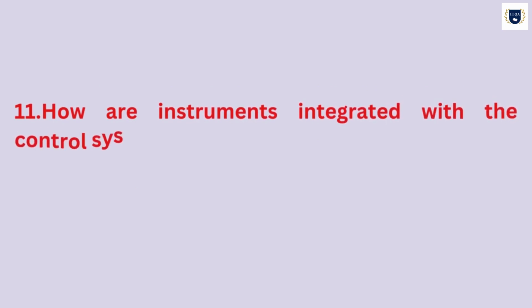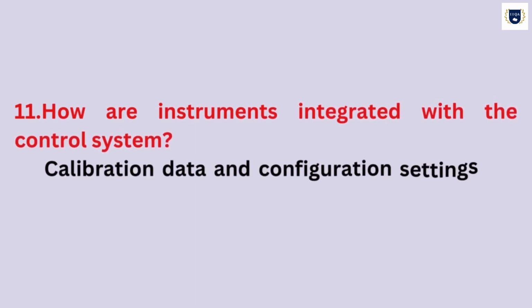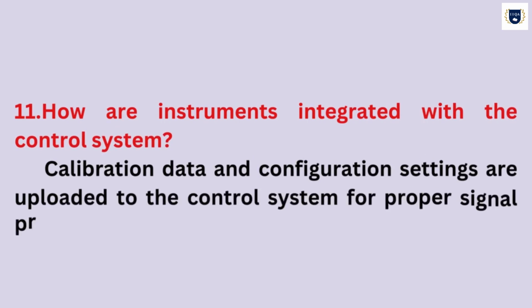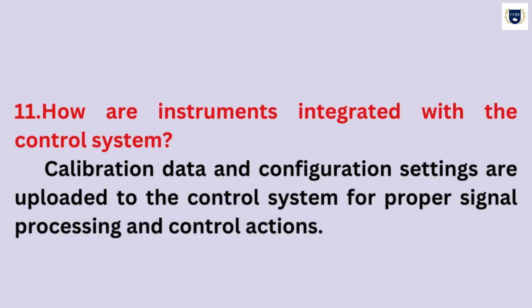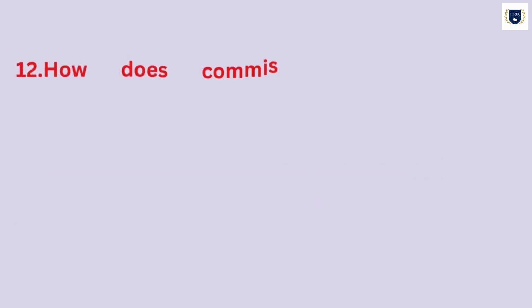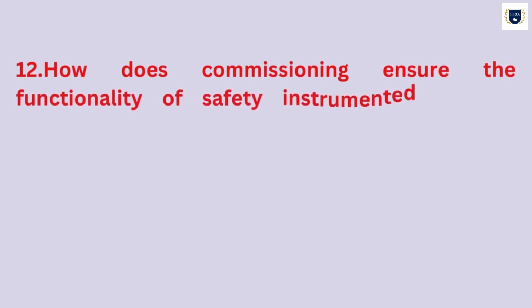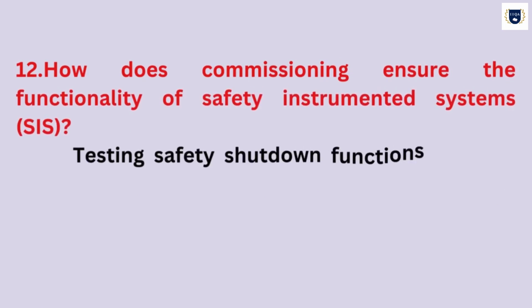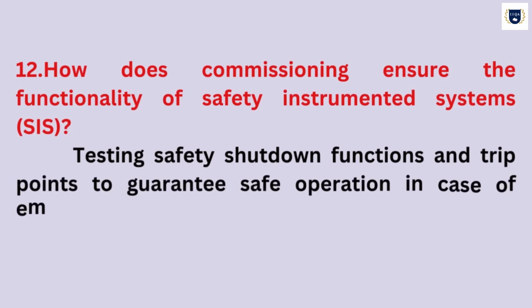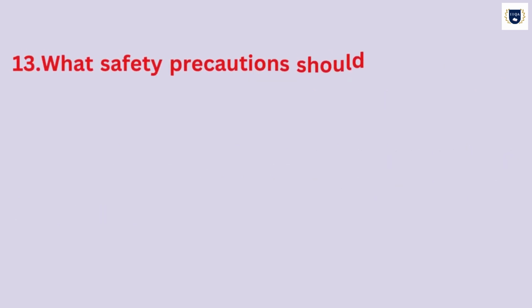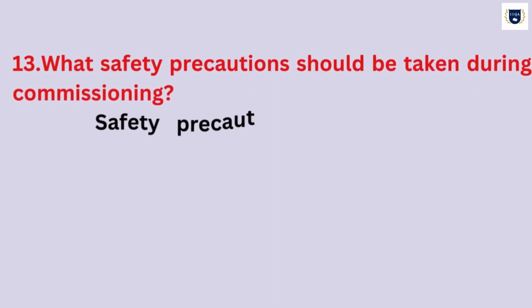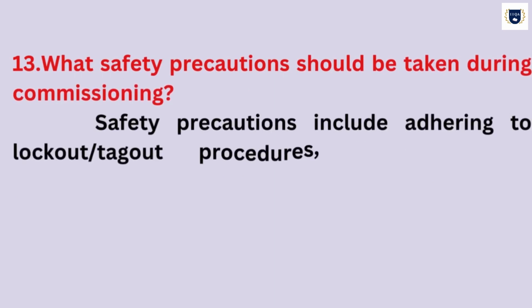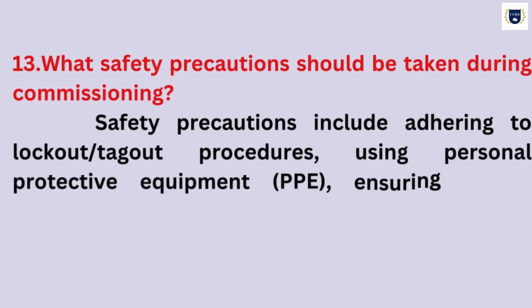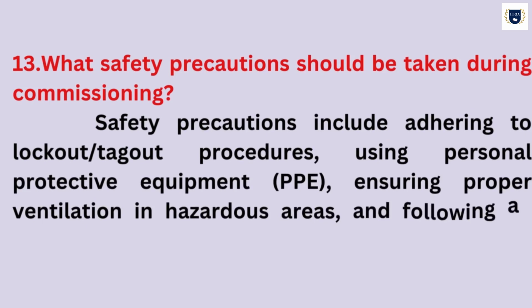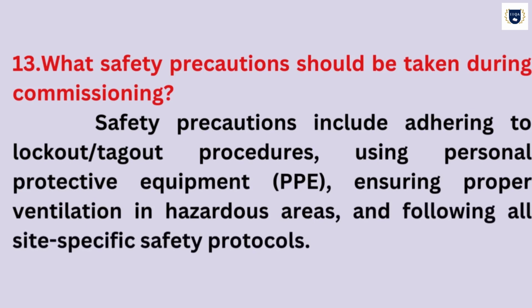How are instruments integrated with the control system? Calibration data and configuration settings are uploaded to the control system for proper signal processing and control actions. How does commissioning ensure the functionality of safety instrumented systems? Testing safety shutdown functions and trip points to guarantee safe operation in case of emergencies. What safety precautions should be taken during commissioning? Safety precautions include adhering to lockout-tagout procedures, using personal protective equipment, PPE, ensuring proper ventilation in hazardous areas, and following all site-specific safety protocols.